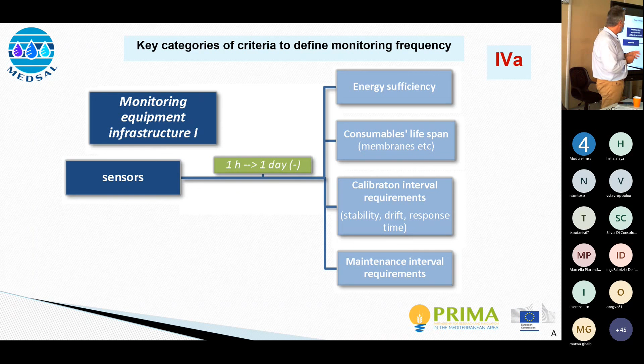Last but not least, maintenance interval requirements - extra important. There's no need for very frequent measurements if you don't respect the maintenance interval requirements; these two have to go hand in hand. Very frequent monitoring with no maintenance is of no use at all. Here, in the green rectangle, you see the suggested window of frequency intervals.